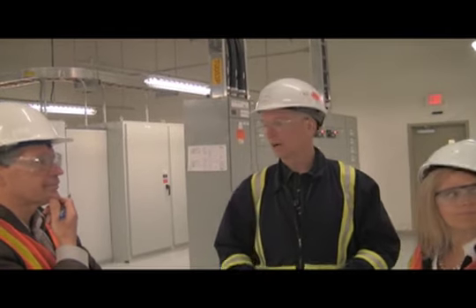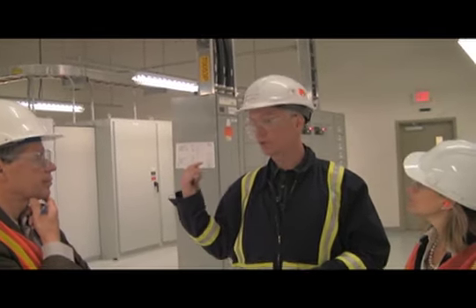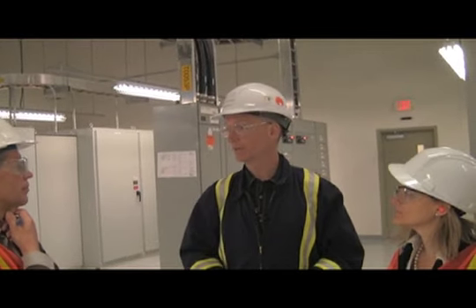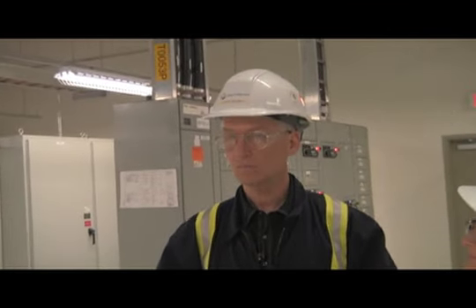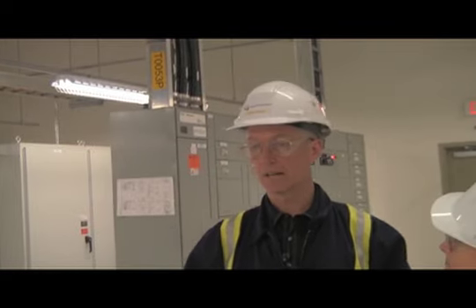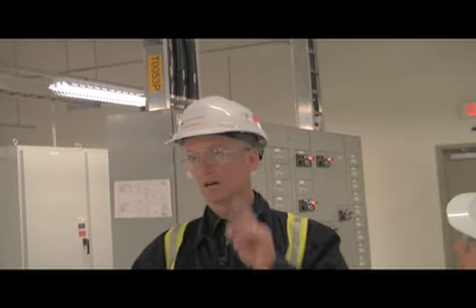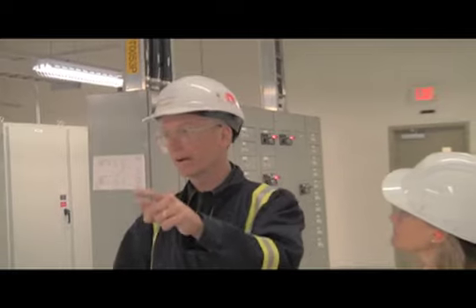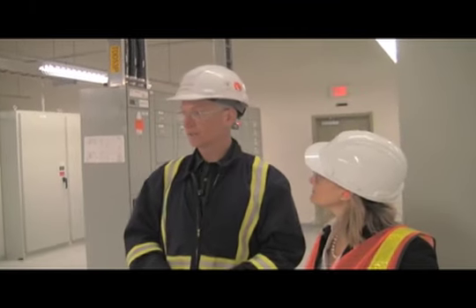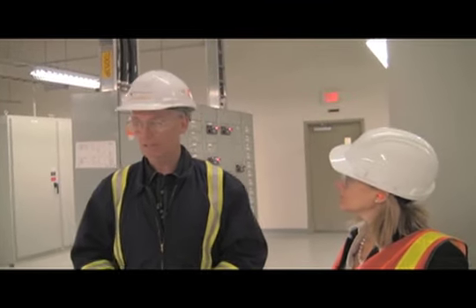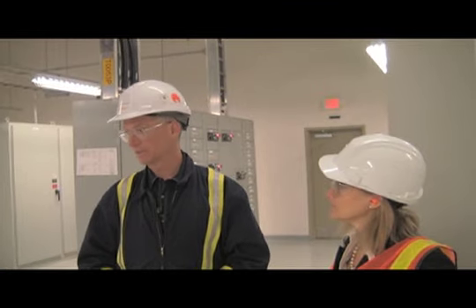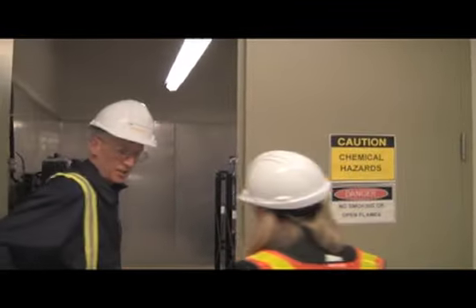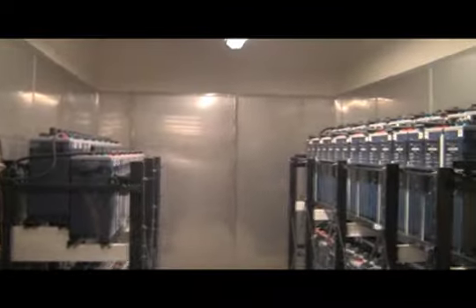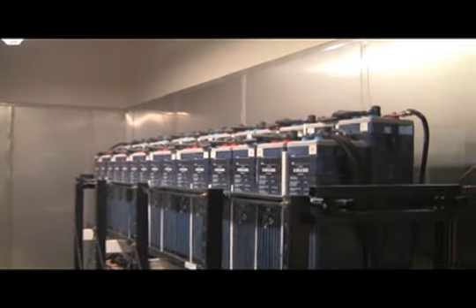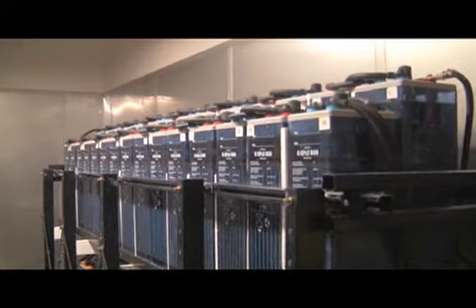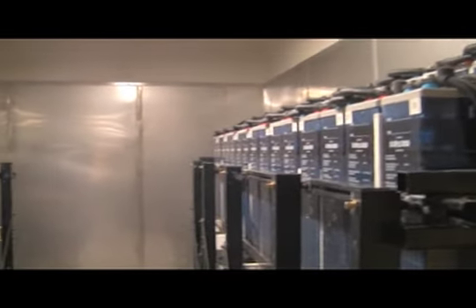All the heavy equipment, if you need the lube oil pumps going for turning gear and whatnot, to keep the lubrication on. And then as an ultimate contingency, behind the switchgear room, there's a battery room. So if the grid has failed and the diesel has failed, we've got batteries that we can go on. You can come in here and take a look. This is one battery bank. Down at the other end of the room, there's another battery bank of similar size.